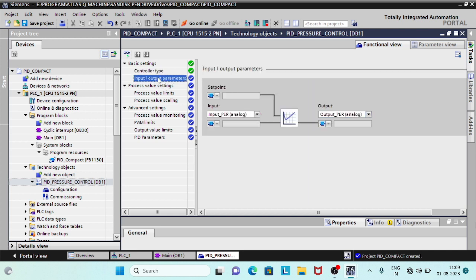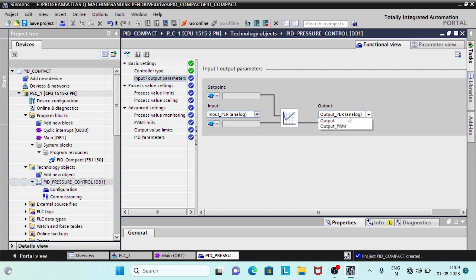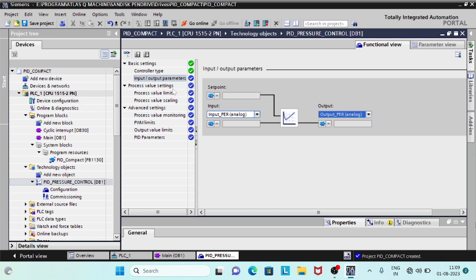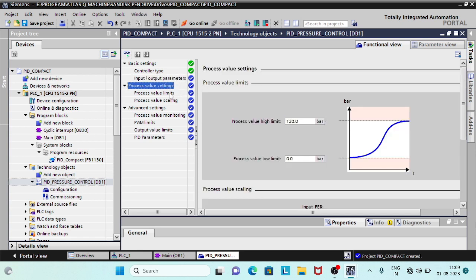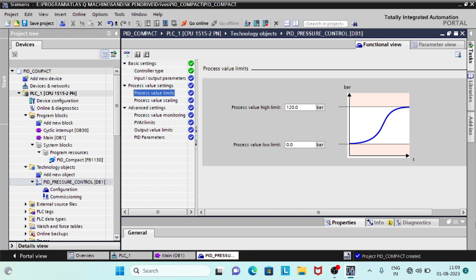In the input/output parameters, we can wire the field IOs. In the input, if we are using a scaled value of the process variable, we will select input. Input PER stands for input peripherals. We will use Input PER to assign the input directly from the field device. In the output, output can be used in three ways. Output PER is used when we are directly assigning analog output to the module. Output is selected when we use a scaled output value. Output PWM is for output as a digital pulse width modulated signal.